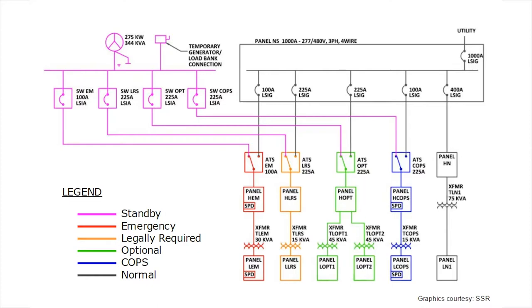This is the one-line diagram for a fairly simple hypothetical facility. It has emergency loads, legally required standby loads, optional loads, and a COPS area. Emergency is in red, legally required is in orange, optional is in green, COPS is in blue, and normal power is in black. I won't talk about COPS. Freddie will talk about that later.